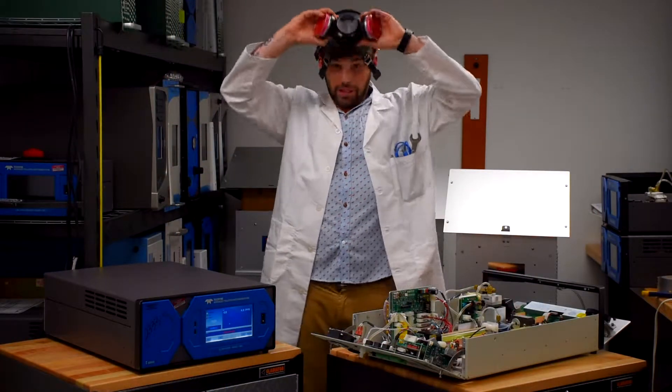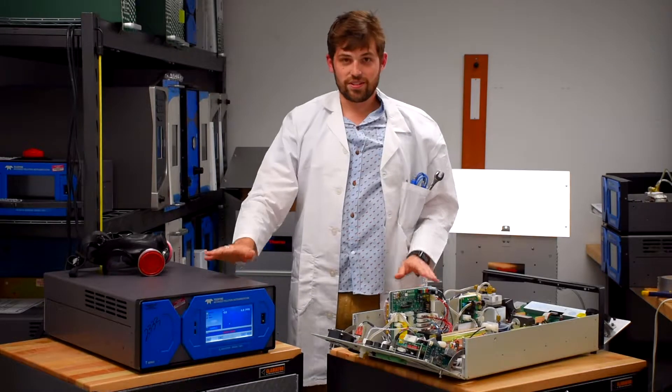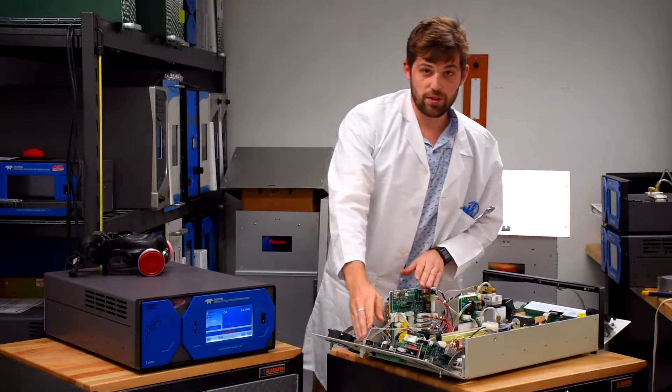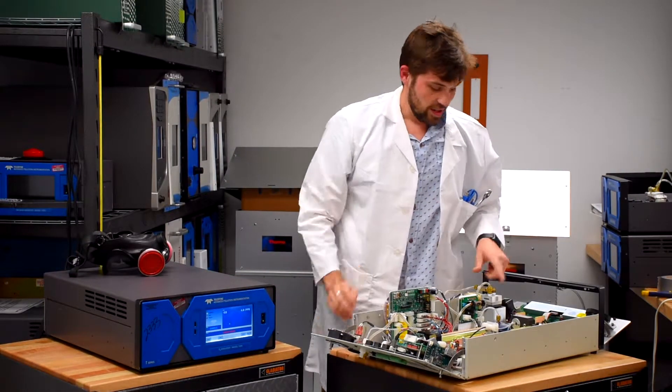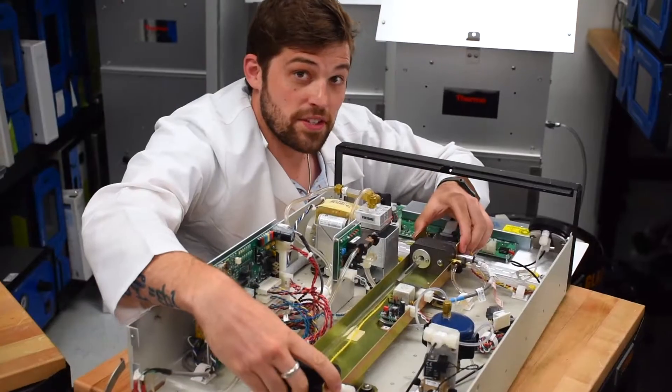That's why we monitor for ozone with analyzers like these. We've got circuit boards that control the instrument, a pump that draws air in, and a photometer where the magic happens. This is the important part.